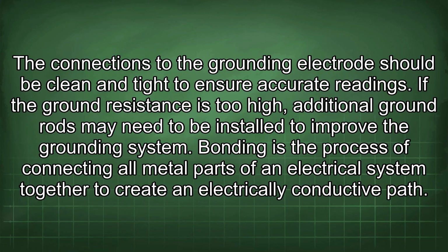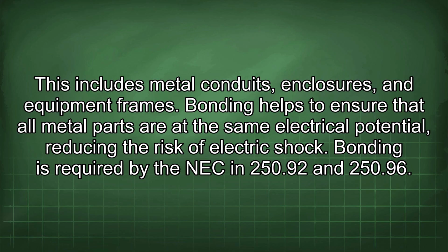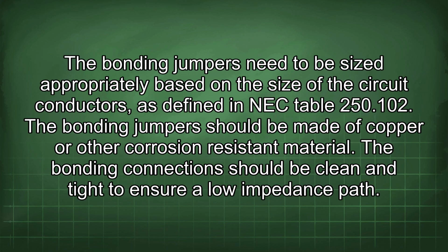Bonding is the process of connecting all metal parts of an electrical system together to create an electrically conductive path. This includes metal conduits, enclosures, and equipment frames. Bonding helps to ensure that all metal parts are at the same electrical potential, reducing the risk of electric shock. Bonding is required by the NEC in 250.92 and 250.96. The bonding jumpers need to be sized appropriately based on the size of the circuit conductors as defined in NEC Table 250.102. The bonding jumpers should be made of copper or other corrosion-resistant material.